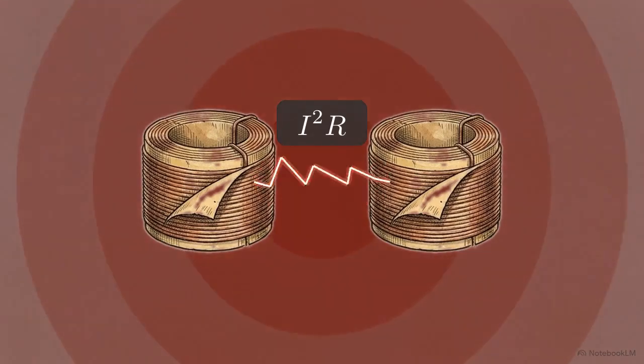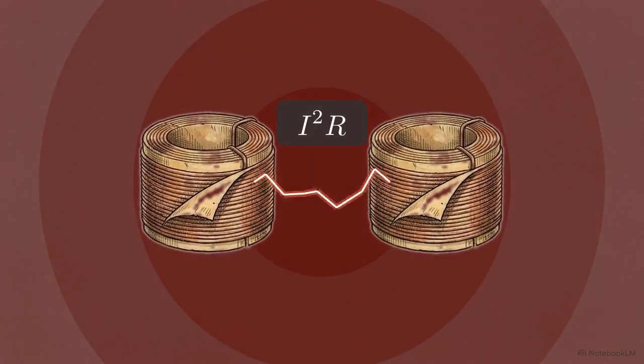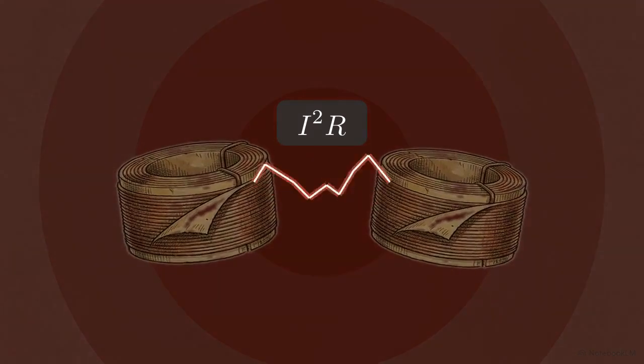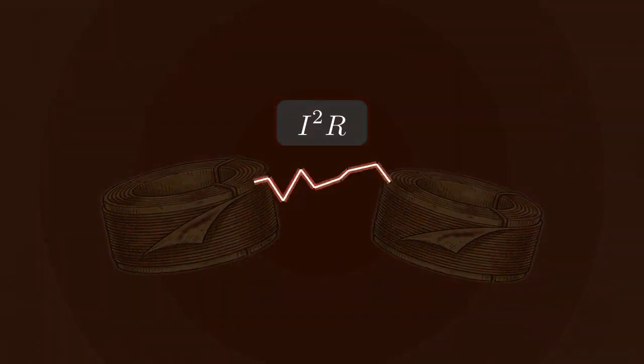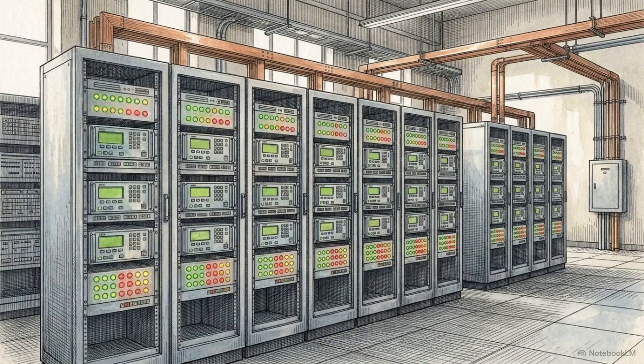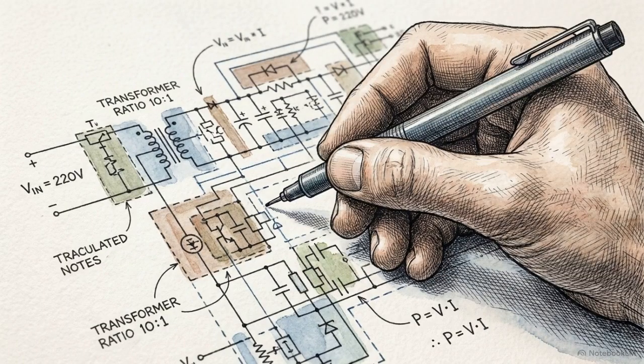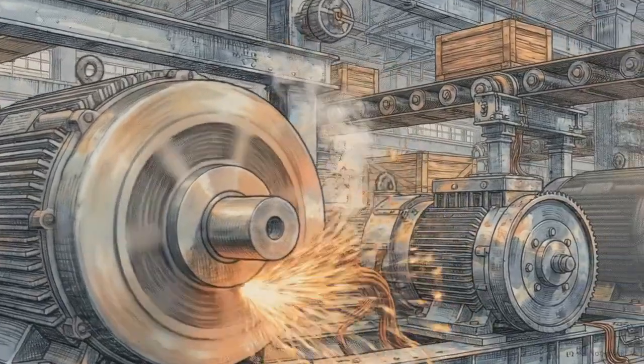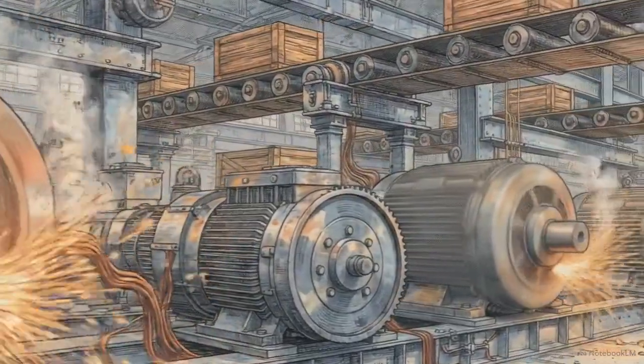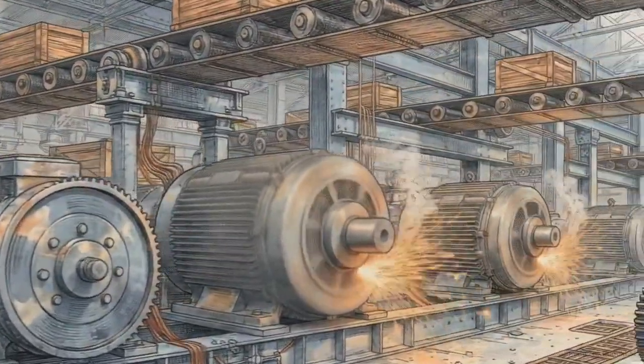If this fault draws current for even a few seconds, the heat load will melt the copper windings, decompose the insulating oil into highly volatile gases, and severely warp the mechanical structure of the core. To prevent this total equipment loss, protective relays must monitor the power flow and isolate the transformer from the broader grid almost instantly. But speed introduces a massive engineering tension. The protection system must be hyper-responsive to genuine faults, yet entirely selective, completely ignoring the harmless temporary surges in current that occur when large industrial loads come online.